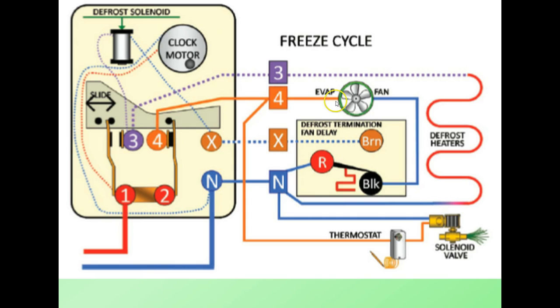This same 115 volts comes out terminal 4. It also goes to the thermostat. Since we're in the freeze cycle, we know the thermostat contacts are made. That power passes through the thermostat to the solenoid valve. The solenoid valve is opened, the compressor is on, and we have our neutral coming back.